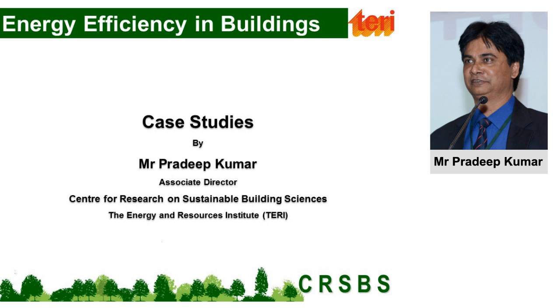Why energy efficiency in buildings? You know that the Central Electricity Authority report, if you look at it, buildings almost consume 30% of the total electricity consumed in a year in India, and industry is just 40%. So building, when I say building sector, it includes both residential and commercial. Residential somewhere around 20 to 22% and commercial 10 to 8%. But intensity is very high, and that's why the focus is on the commercial buildings, and more and more buildings are going to be constructed.